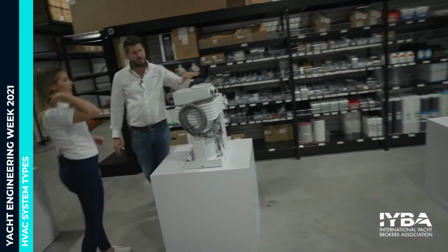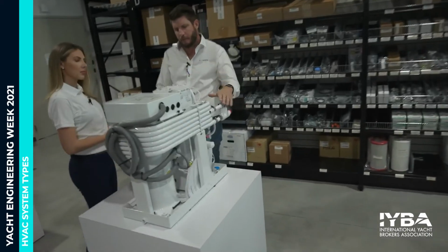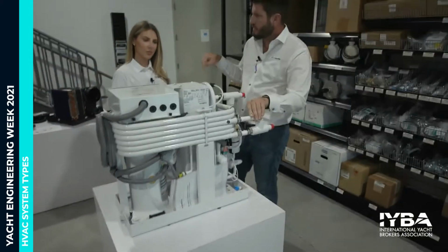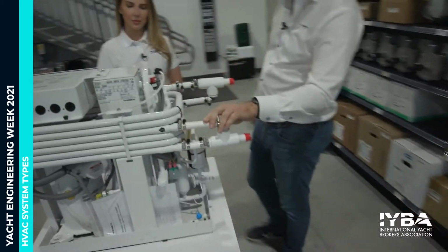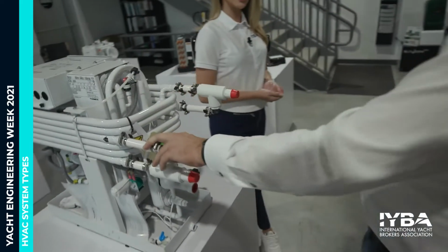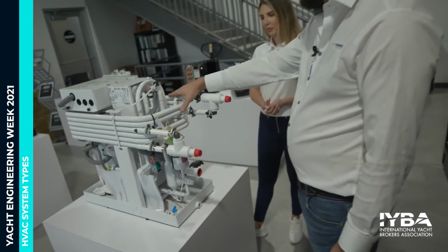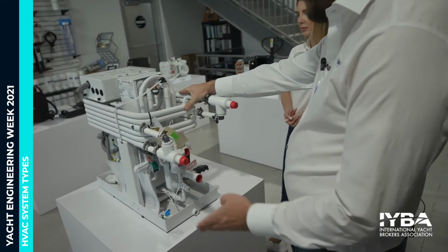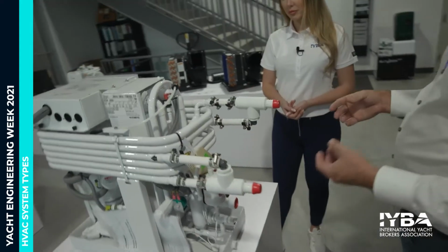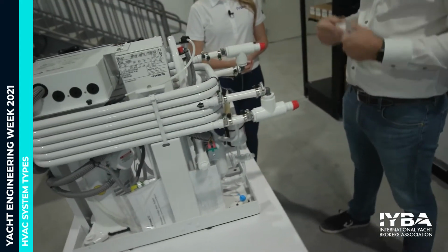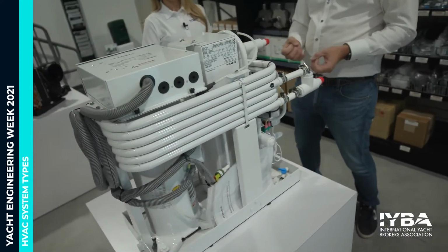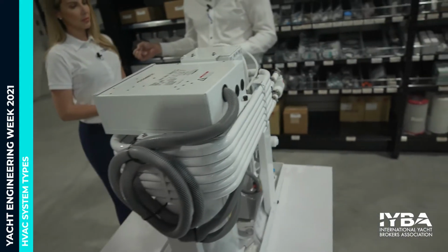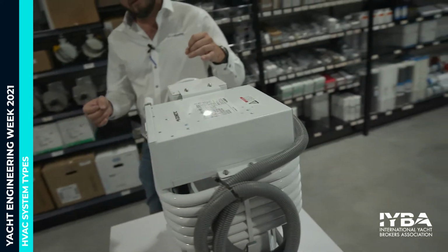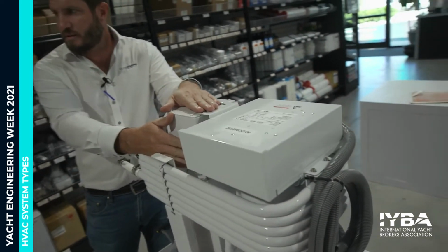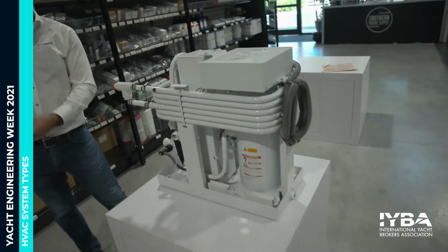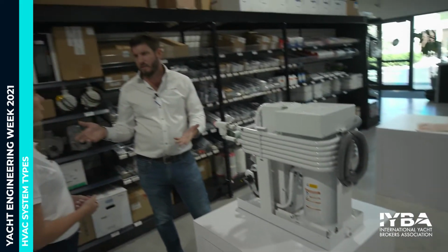This is more of a hydronic system—instead of sending refrigerant throughout the boat, we send chilled water throughout the boat. The benefit is you can have, say, two or three chillers in the engine room, all working together as a team cooling the same chilled water loop. The chilled water circulates through the boat, and there's redundancy built in—if compressor number one fails, compressors two and three keep cooling the loop, so the master stateroom still gets air conditioning.